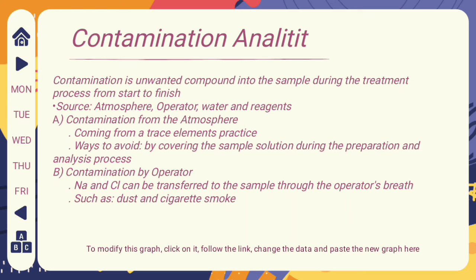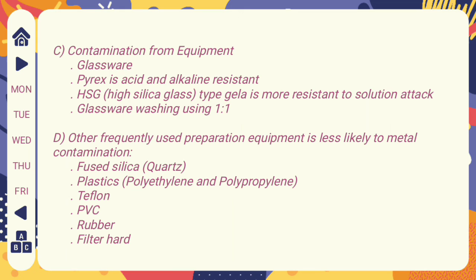C. Contamination from equipment. Glassware Pyrex is acid and alkaline resistant. High silica glass is resistant to solution attack. Glassware washing using 1-to-1 acid. The other frequently used preparation equipment is less likely to cause metal contamination: silica or quartz, plastic, polyethylene and polypropylene, Teflon, PVC, rubber, filter hard.